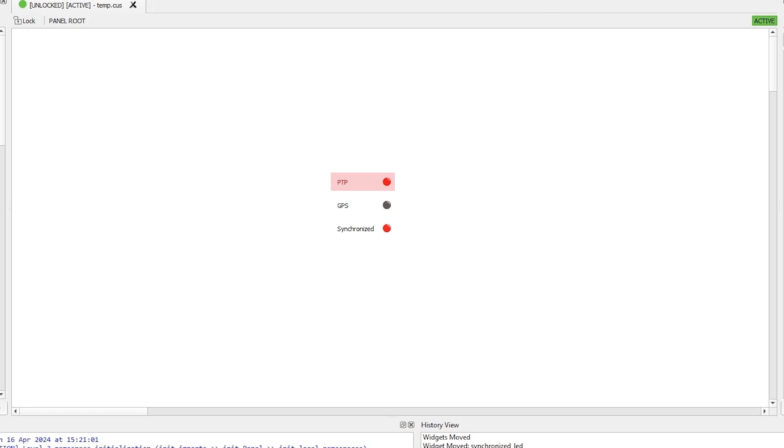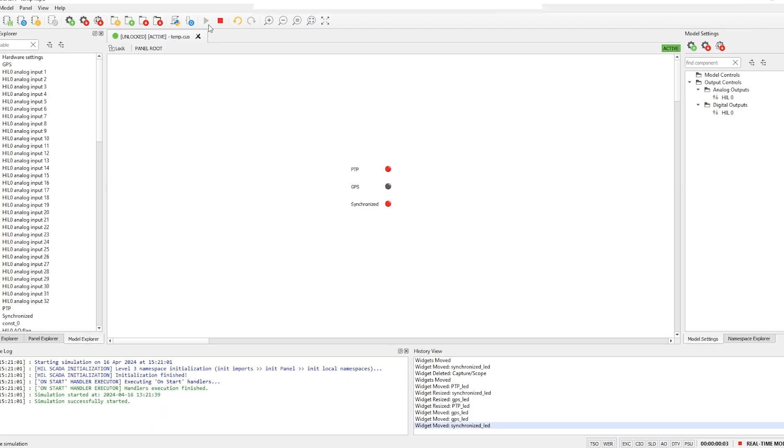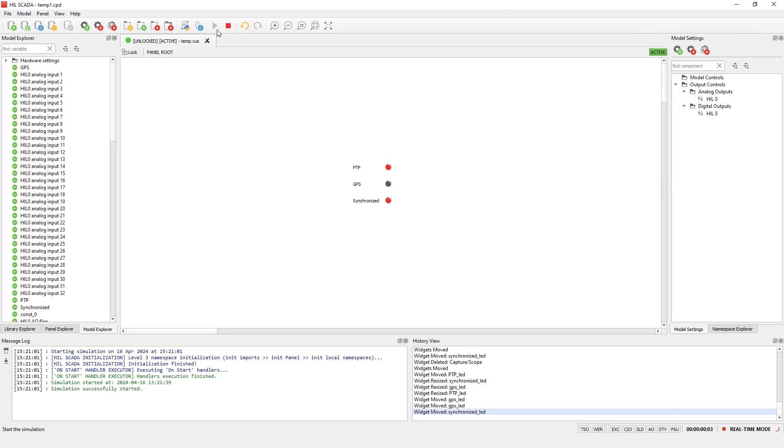PTP indicates the presence of the external PTP source. A value of 1 indicates that the system is actively being synchronized. Since IRIG-B is not active in this example, the GPS LED will be off all the time. The synchronized LED indicates whether the HIL device has achieved full synchronization or not.